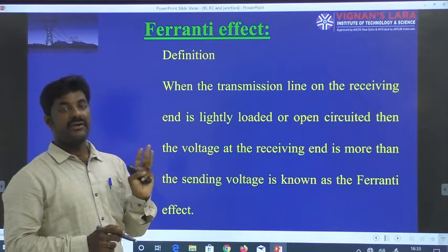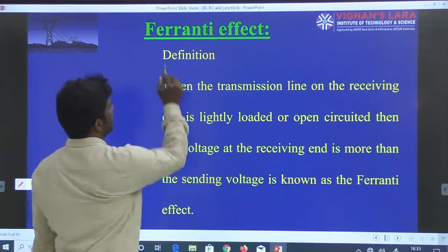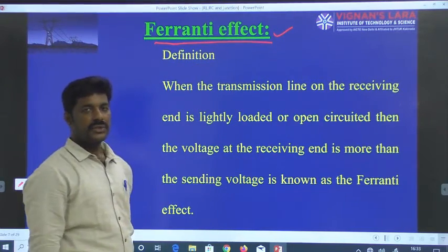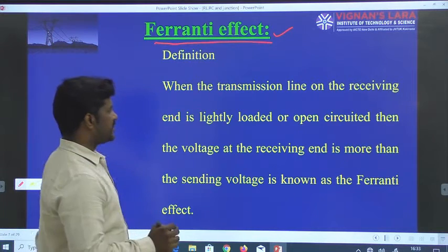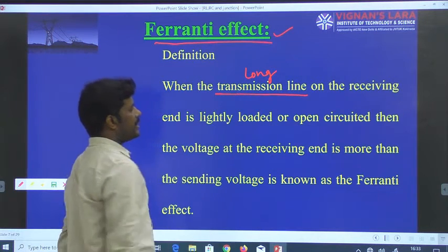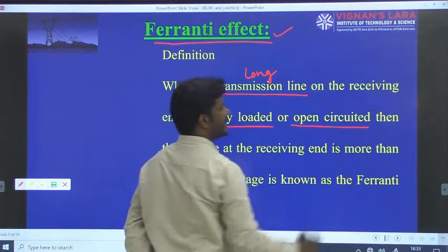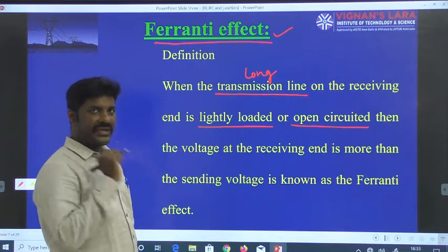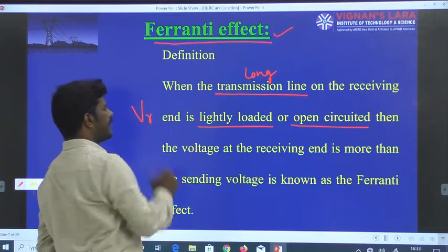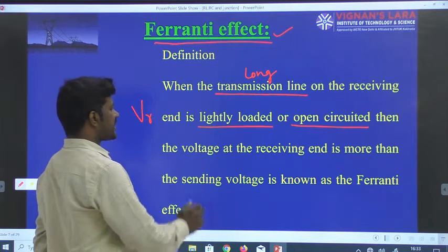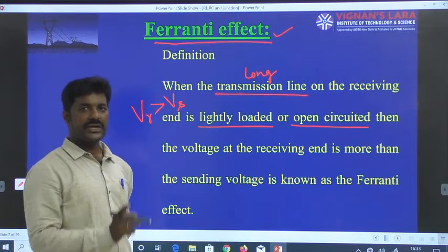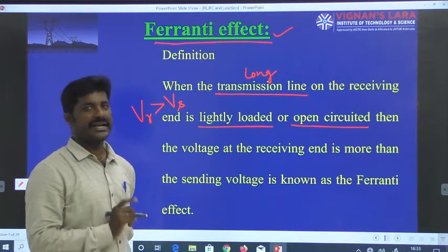And the third effect is the Ferranti effect. Then what is meant by Ferranti effect? Whenever a long transmission line, especially the line should be a long transmission line, is operated under lightly loaded condition or open circuited condition, then on the receiving end side, the voltage VR is observed to be greater in magnitude than the sending end voltage Vs, where VR is the voltage at the receiving end side and Vs is the voltage at the sending end side.